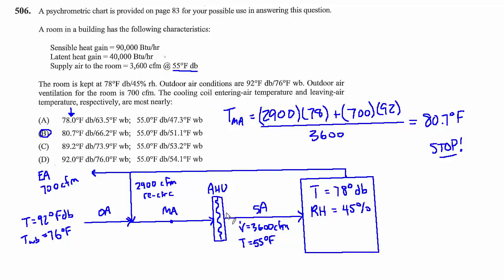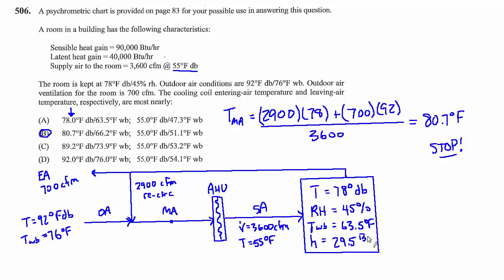For practice, let's also find the wet bulb for the mixed air and for the supply air. Just as we did a mixed air calculation for dry bulb, we can do something similar for wet bulb. The conditions in the room are fully defined, so let's look up a few more values from the psychrometric chart. At 78 degrees dry bulb and 45% relative humidity, the wet bulb temperature is 63.5 degrees Fahrenheit, and the enthalpy inside the room is 29.5 BTU per pound.